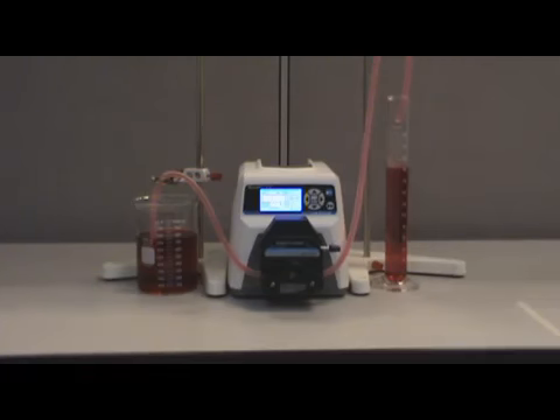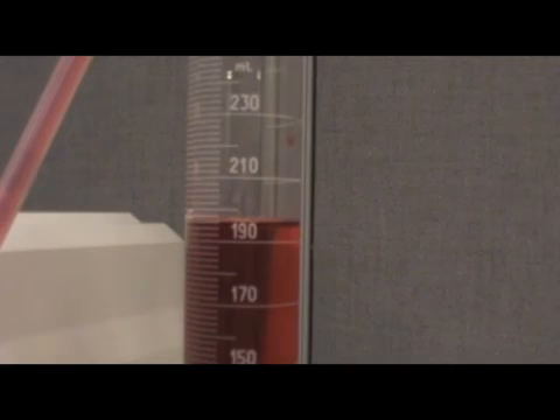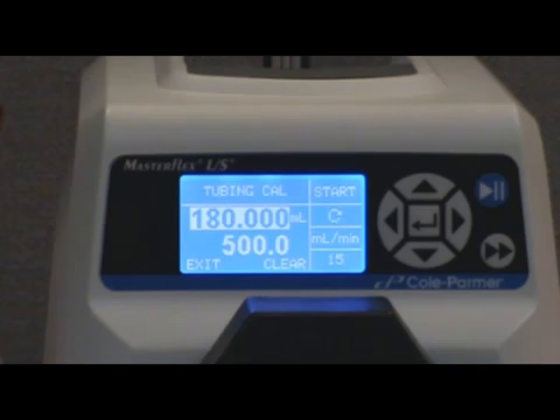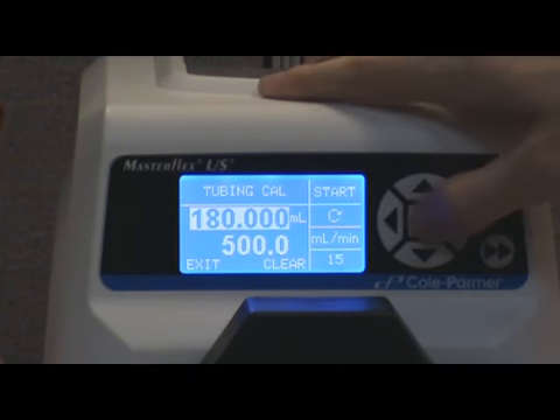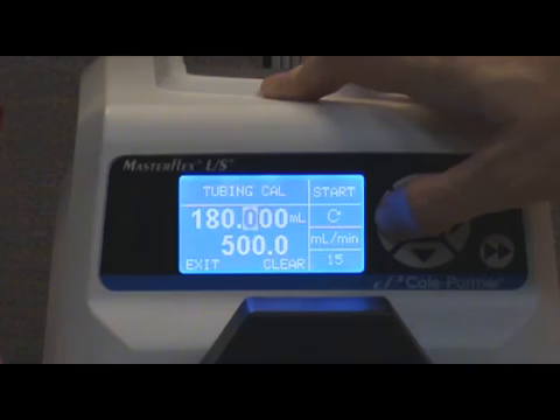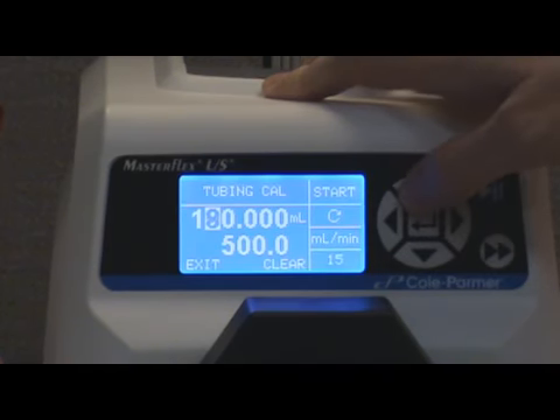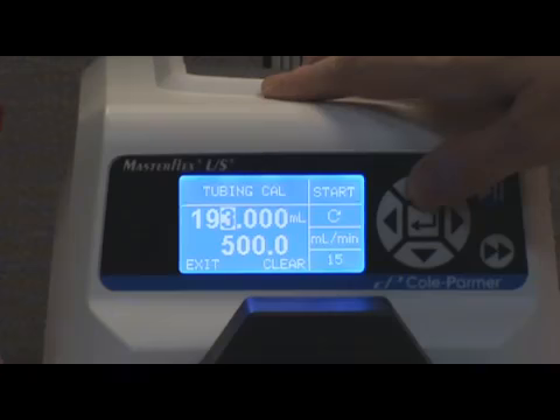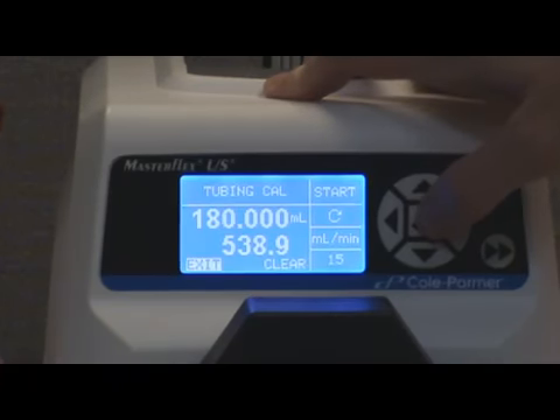After the pump is stopped, read the amount in the graduated cylinder. Be sure to read the bottom of the meniscus in order to obtain accurate results. After reading the volume in the cylinder, the cal volume field will be highlighted. Press the enter button and adjust the volume to match your result. The volume that was pumped in our example was 194 milliliters. Then press the enter button once more to confirm your value.